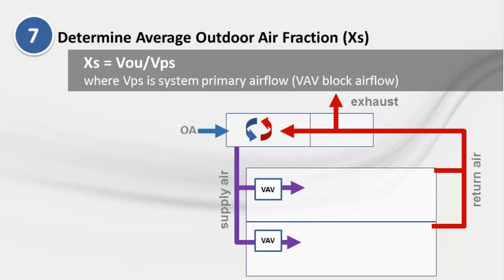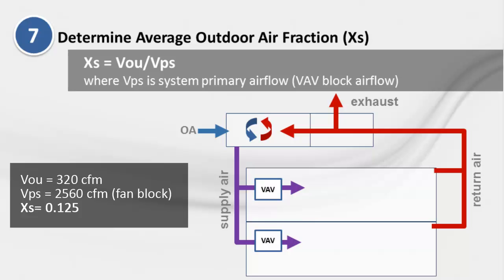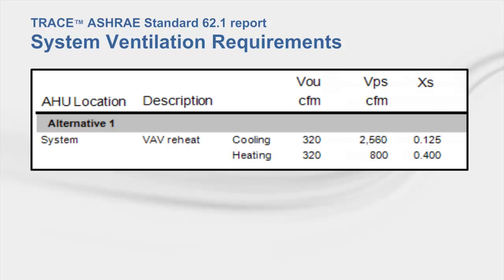Next, the average outdoor air fraction, X sub S, is calculated by dividing the uncorrected outdoor air intake by the system primary air flow, V sub PS, which is the fan design air flow. In TRACE 700, V sub PS is reported as V sub fan on the ASHRAE Standard 62.1 report and is also equal to the main fan air flow found on the system checksums report. The uncorrected outdoor air fraction, X sub S, is shown in the System Ventilation Requirements section of the TRACE 700 report.